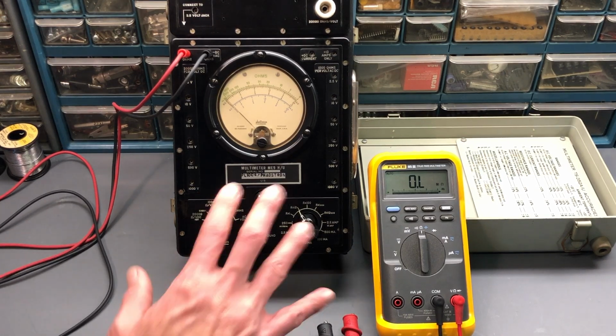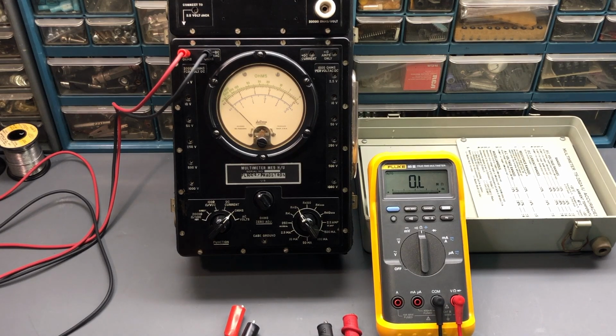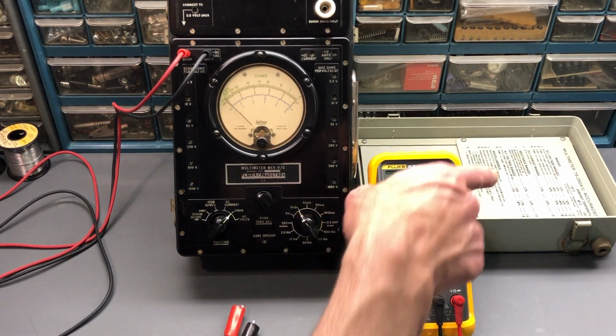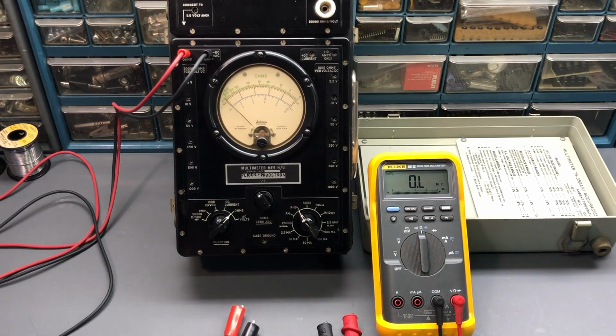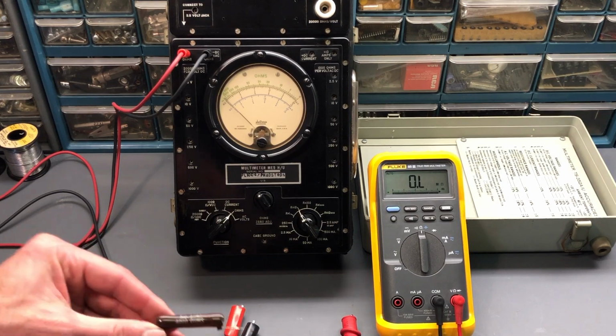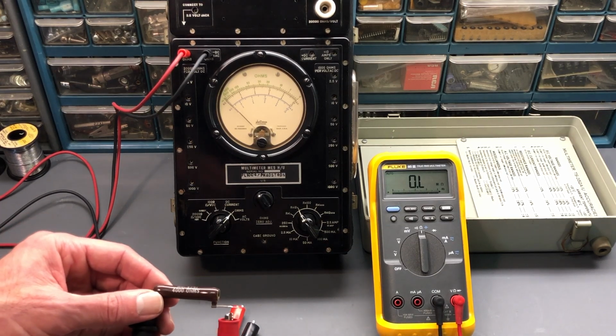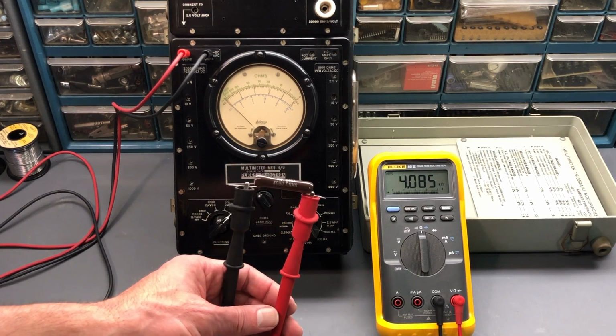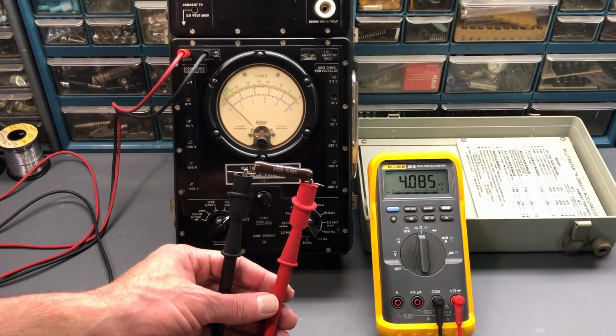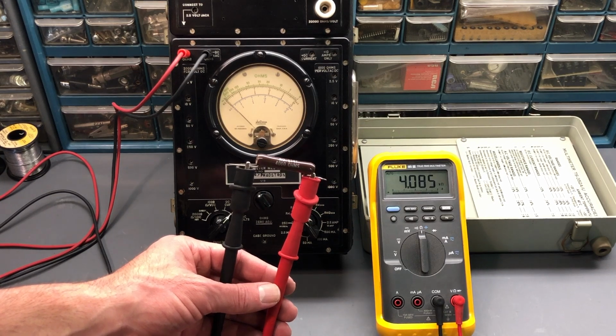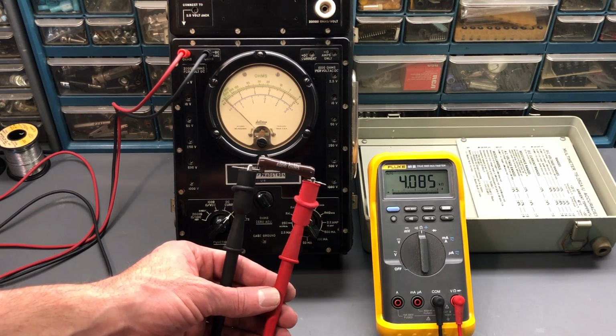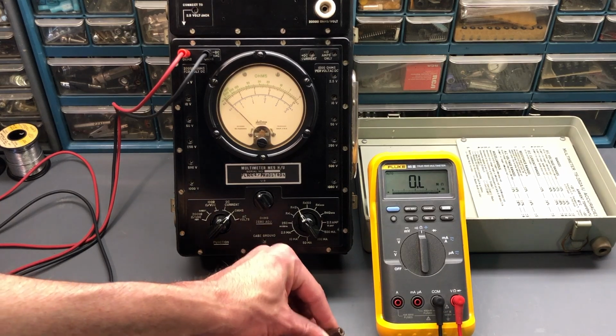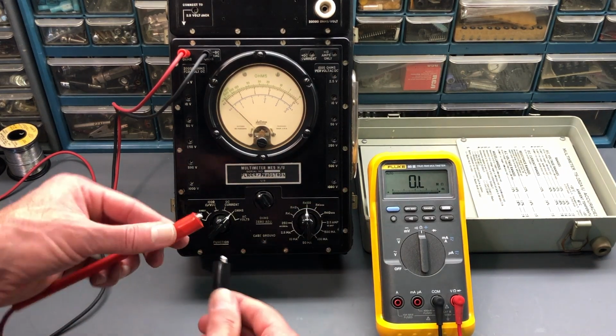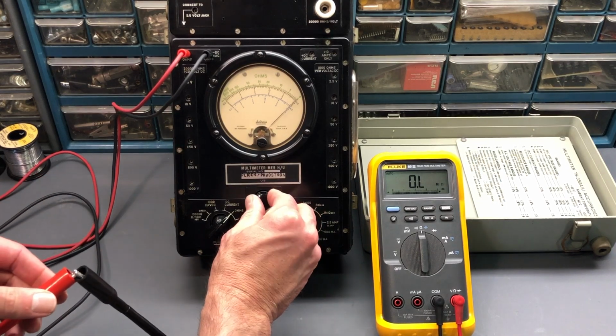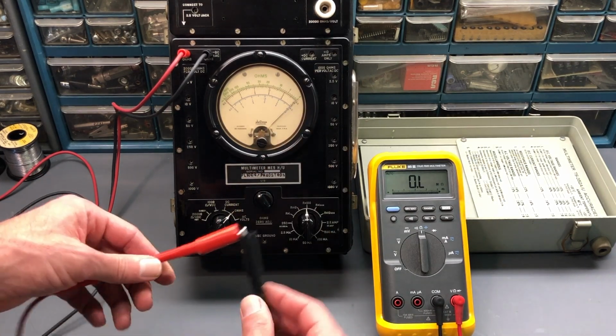Analog meters always have some error that you have to account for, which is actually what's printed in the top cover over there. It talks about the percent error that you can expect. Okay, the next resistor is marked 4,000 ohms, 4K ohm. So 4.085, almost 4.1, so 4.08. All right. So we'll go up to the next range, short the leads together, right on 0, no problems there.